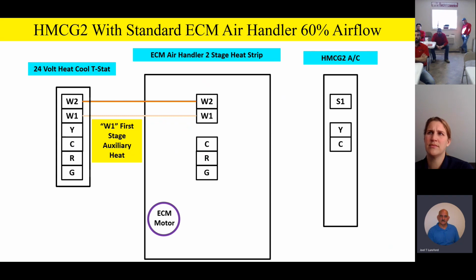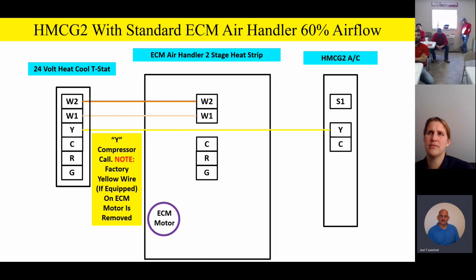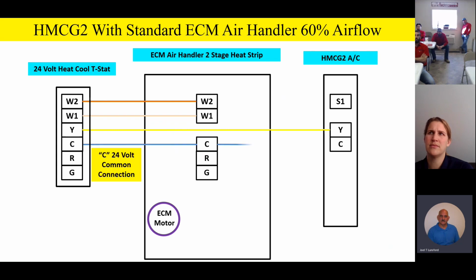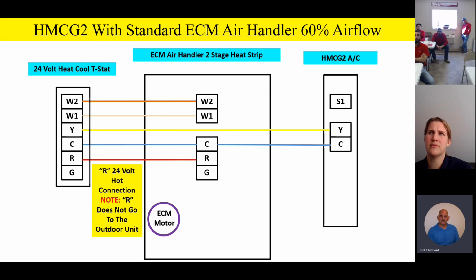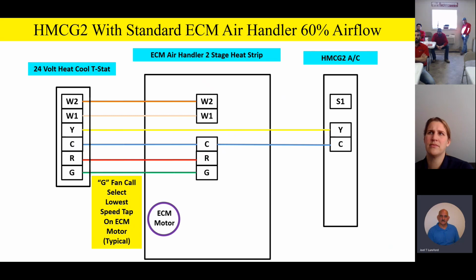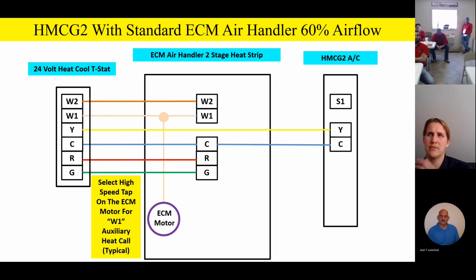Again, it's just a straight cooling product. You'll notice there's a Y that goes straight outside. C is 24 volt common. R is 24 volt hot, and it does not go to the outdoor unit, just like we had before. And on the G, that's your fan call. Typically, just like we did before, G will be our lowest speed tap, is how we typically find that hooked up. You'll also notice that on the high speed tap of the ECM motor, go ahead and grab your auxiliary heat. So again, we're going to drive the auxiliary heat fan speed to 100% airflow, or high airflow, so we don't overheat the heat strip.